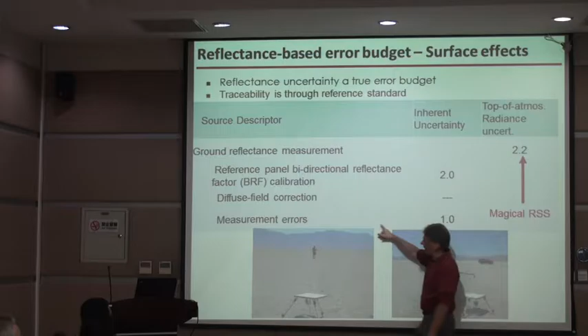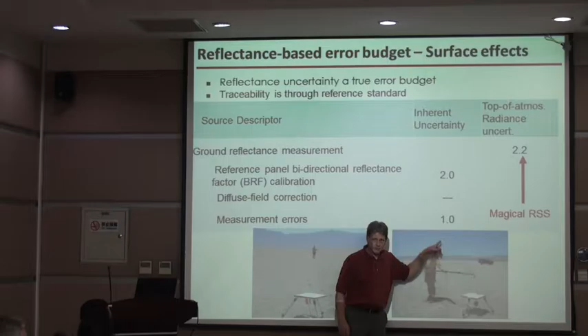In the ground reflectance measurements, we basically have three pieces here: the reference panel bidirectional reflectance calibration, the diffuse field correction, and the measurement errors. The reference panel bidirectional reflectance factor is based on somebody at the University of Arizona computing all of the things that go into the calibration of the reference panel. The PTFE reference coming from NIST, the operation of the radiometer in the black lab, the operation of the lamp in the black lab, the spectral stability of all the instruments in the laboratory. All of that was done in an excellent way to get a true error budget of 2.0%, and that's been validated through round-robin experiments.